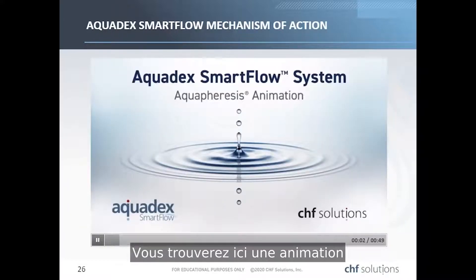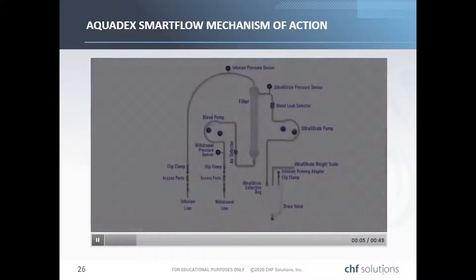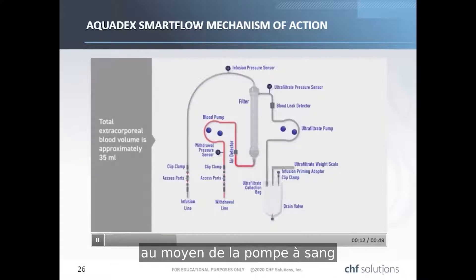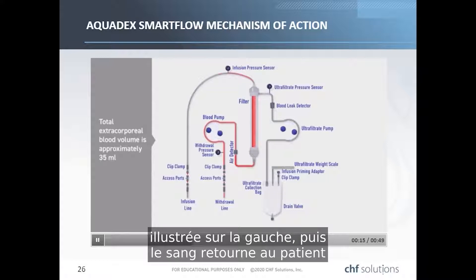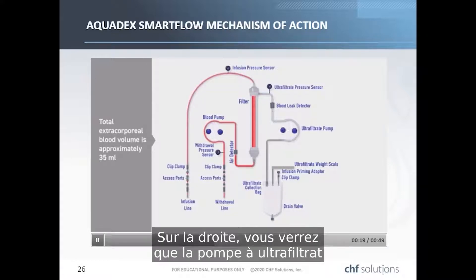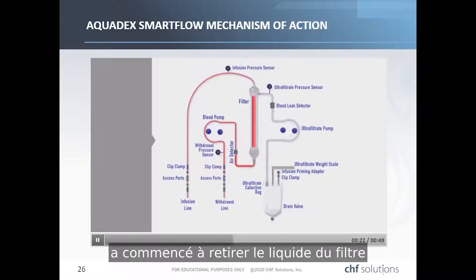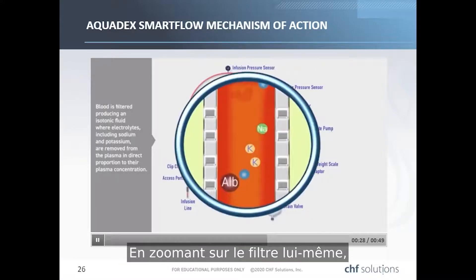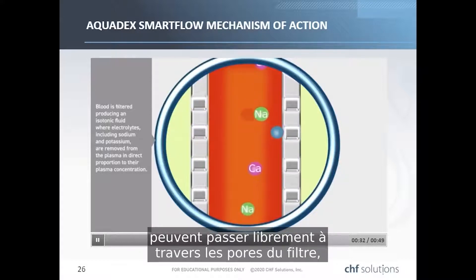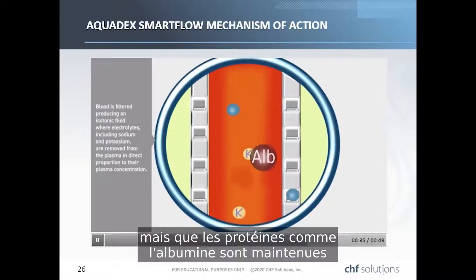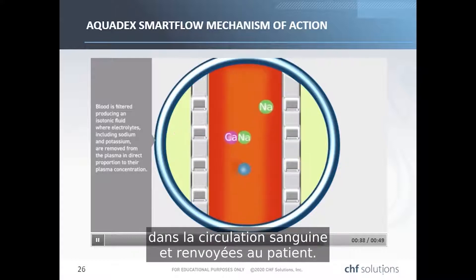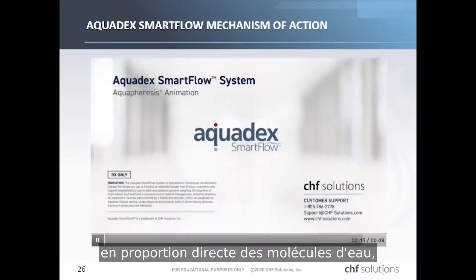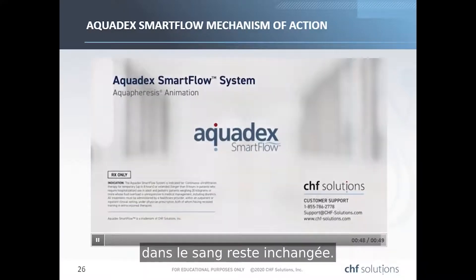The Aquadex system blood circuit works as follows: blood is withdrawn from the patient by the withdrawal line and pushed through the filter by the blood pump. The blood then returns to the patient via the infusion line. The ultrafiltrate pump withdraws fluid from the filter and collects it in a UF bag. Water molecules and electrolytes freely pass through the filter pores, while proteins like albumin are maintained in the bloodstream and returned to the patient. Because electrolytes are extracted in direct proportion to water molecules, the concentration of electrolytes in the blood remains unchanged.